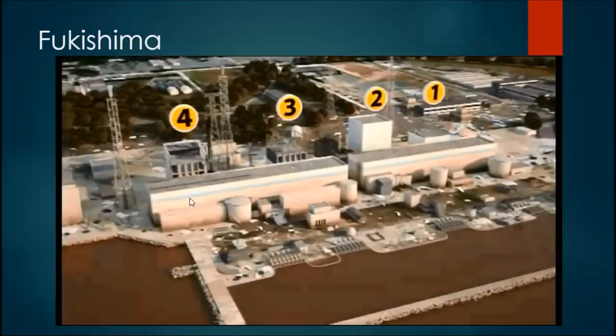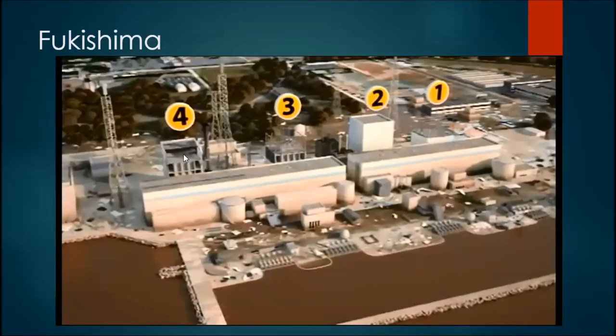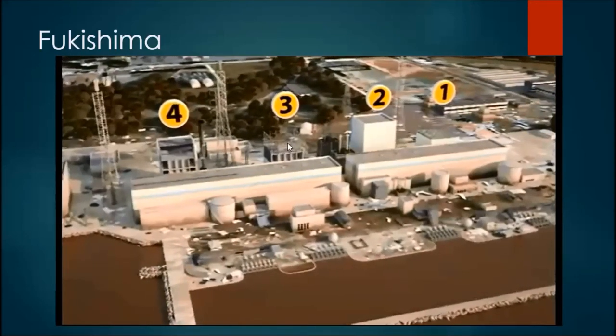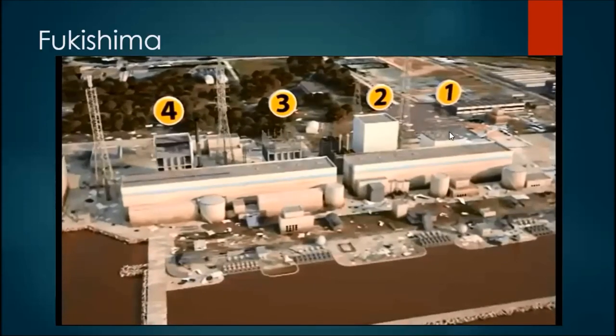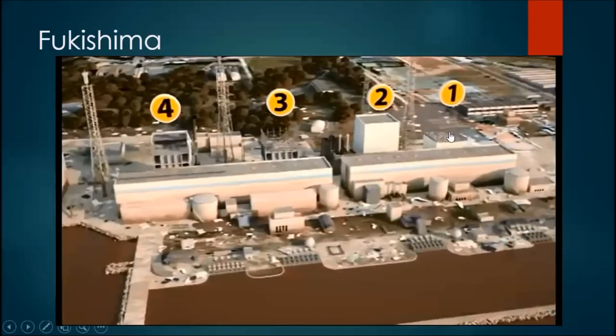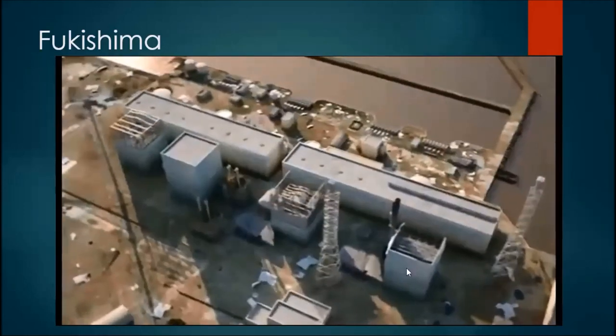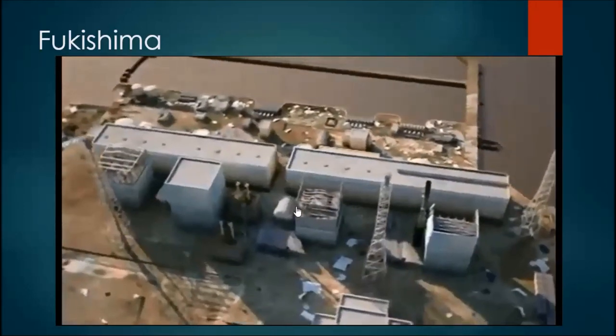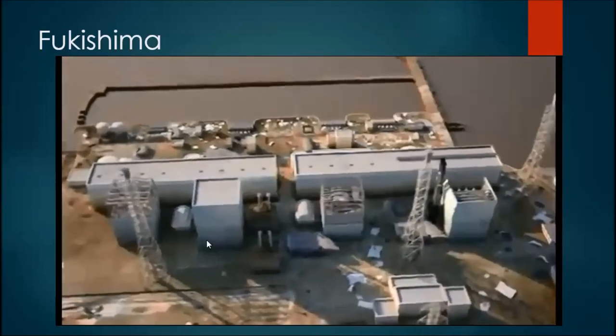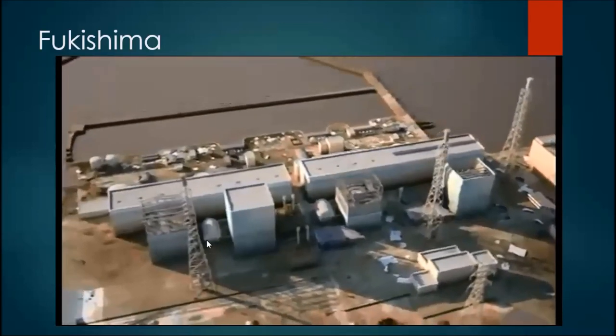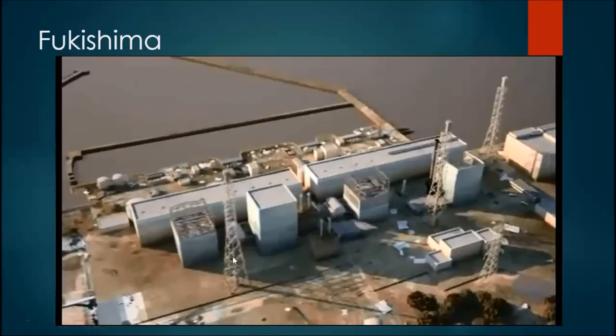Gradually, the situation began to stabilize. By the end of March 2011, fresh water had replaced seawater. In July, the reactor cooling system was again in operation in closed circuit, thereby avoiding discharges of contaminated water into the environment. In December 2011, Japanese authorities officially declared that the nuclear power plant reached the cold shutdown state, an expression used when the cooling water does not evaporate anymore and remains liquid below 100 degrees Celsius.